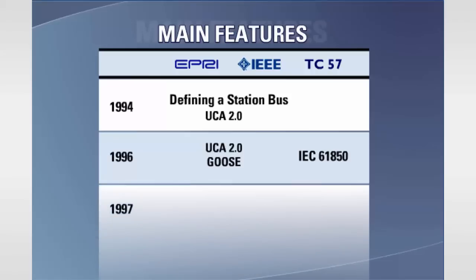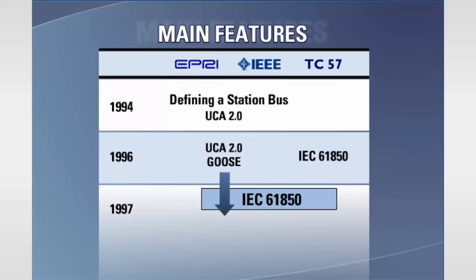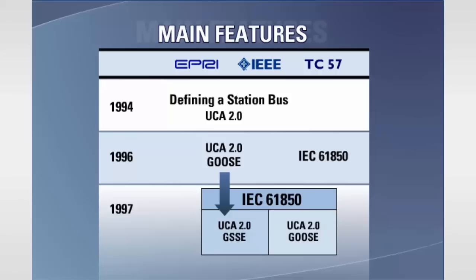In 1997, the UCA Committee and Technical Committee 57 agreed to work together to define a common international standard, which resulted in the current IEC 61850 specification. Within this new specification, the UCA 2.0 GOOSE was renamed Generic Substation State Event or GSSE and an enhanced GOOSE was specified. The IEC 61850 peer-to-peer service is the UCA 2.0 GOOSE with enhanced functionality. The IEC 61850 station bus also specifies a client server model which we'll look at later in the course.